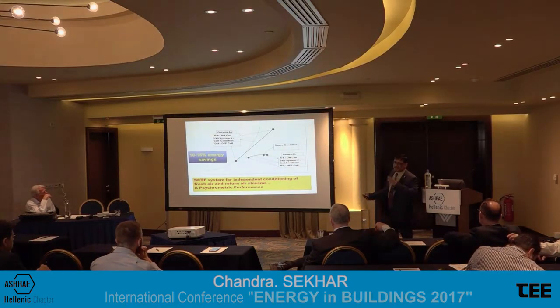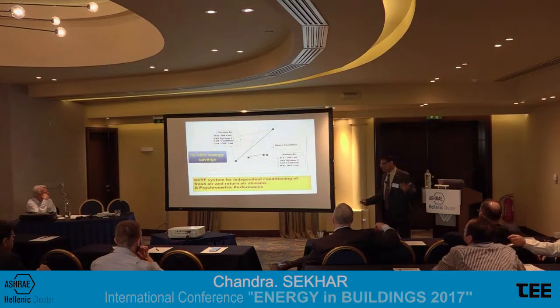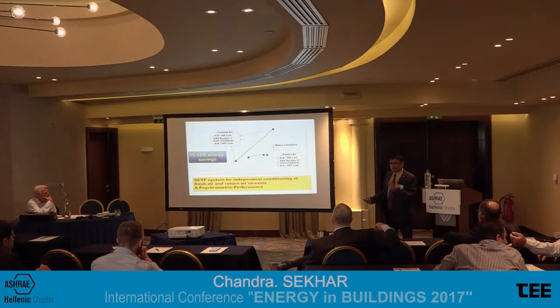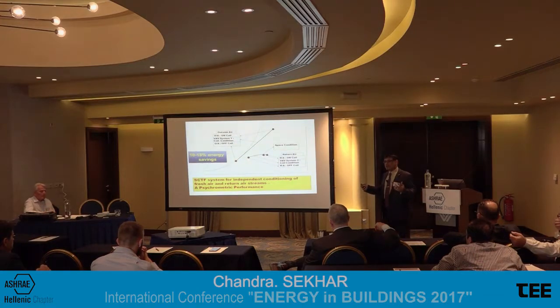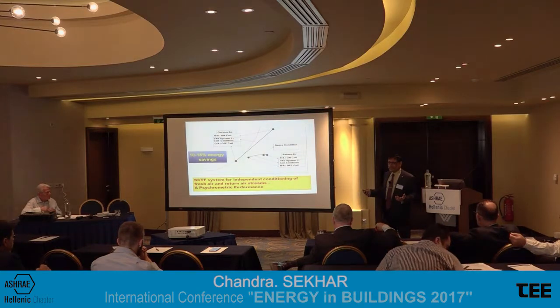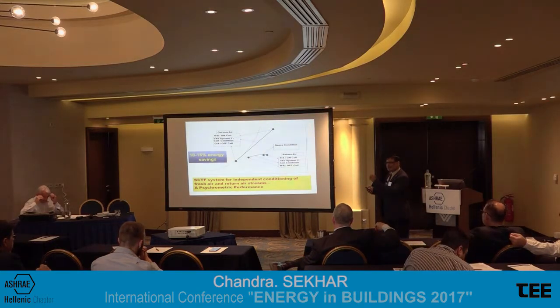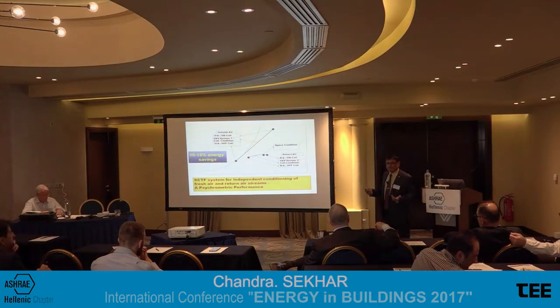If you look at 62.1, I've been in 62.1 for more than 10 years now, I'm still part of the committee there. If you follow the multi-zone variable air volume design, you've got to ensure that in the worst case scenario, what's called the critical zone load, which is a not so hot day, overcast condition, you have other spaces not having high occupancy demand, but you've got that one seminar meeting or conference room that's fully occupied. It's going to require a high level of ventilation air, percentage of ventilation air.